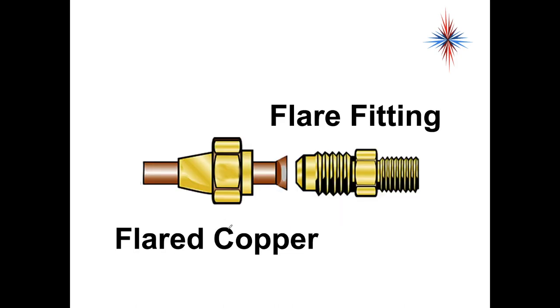So when all things go together, you have your flare fitting and the flared copper, and that nut fits exactly over that flare and pulls this down. It makes a really good solid seal that will last for years. You do not need to use pipe dope or any other sealant on good flared fittings.